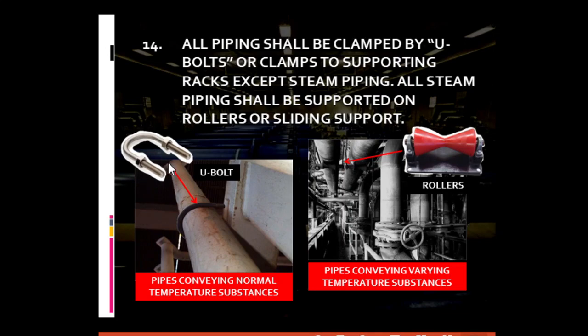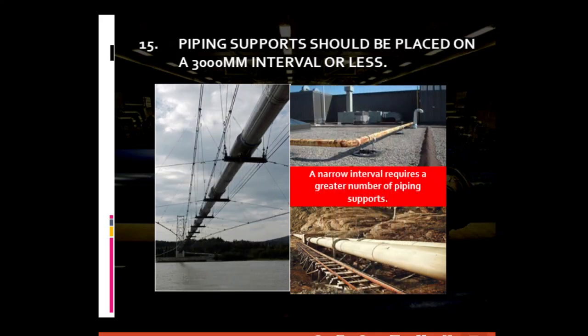Shown here are a U-bolt and a roller pipe support. For general piping requirement number fifteen: piping supports should be placed at a 3,000 mm (3 meter) interval or less. The proper location and number of piping supports is important to prevent possible collapse of the piping system. Too many piping supports prevent collapse but result in unnecessary expenses. Using too few supports lowers initial investment cost but leads to higher expenses in the long run due to the strong possibility of pipe system collapse.